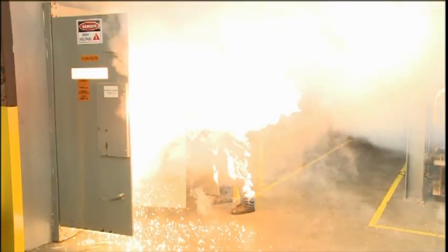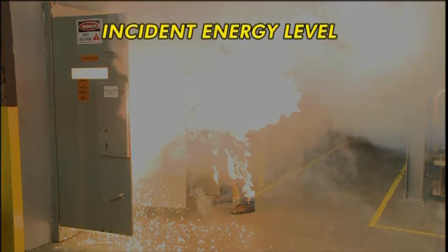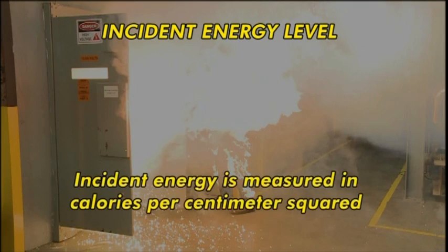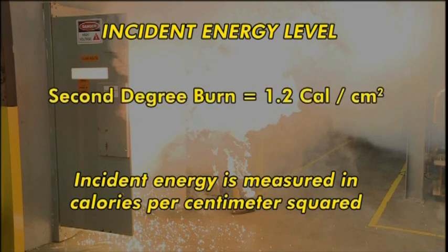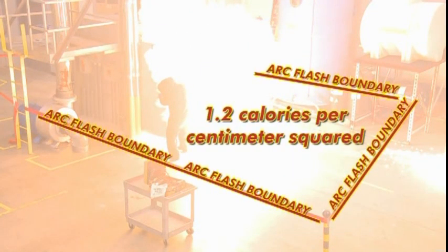The amount of heat energy available to burn you during an arc flash is called the incident energy level. Incident energy is measured in calories per centimeter squared. The amount of heat energy that will cause a second-degree burn on unprotected skin is 1.2 calories per centimeter squared. The arc flash boundary is established at the distance from a potential arc source at which the incident energy level is determined to be 1.2 calories per centimeter squared. In other words, the arc flash boundary is the distance from an arc source where an unprotected worker will receive a second-degree burn.